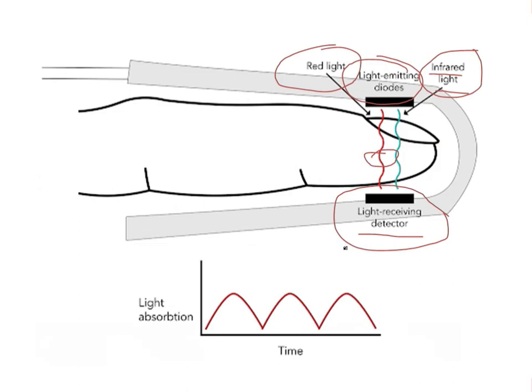We will take the ratio between the deoxygenated hemoglobin and the oxygenated hemoglobin, and we will use the microprocessor in the machine. This ratio will be correlated with an algorithm already saved in the microprocessor. Experiments done on volunteers correlate the ratio and the oxygen saturation.